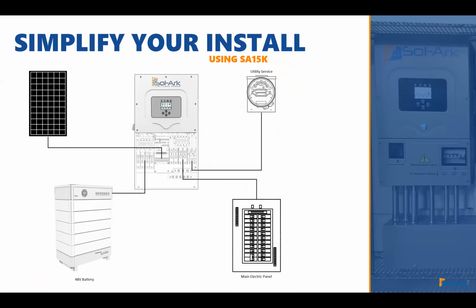Also, since we are an all-in-one installation, this is an example of simplifying your install. All you need for external parts and pieces will be your PV array, a 48-volt battery, your backup panel or your main electric 200 amp panel, and then your utility service. The only extra piece that you'll see in between here is typically an AC disconnect between the utility and the grid connection of the Sol-Ark inverter.